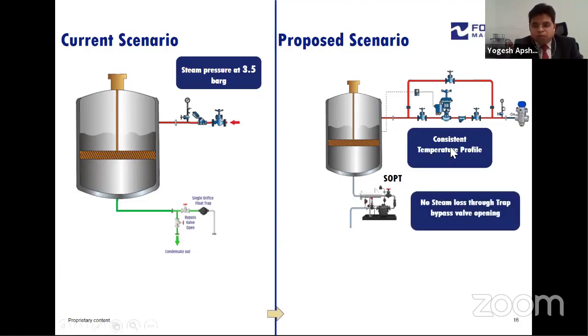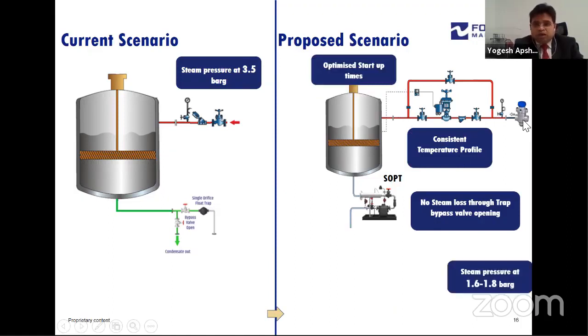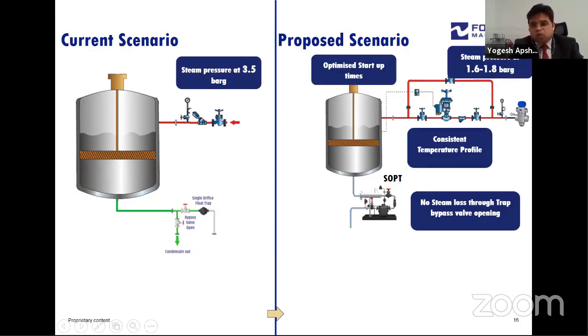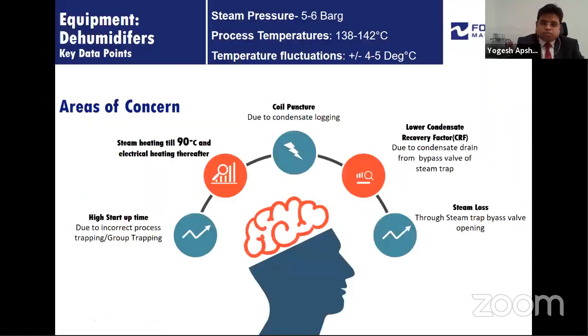So we put a PID based temperature control valve which makes a consistent temperature profile. Then optimize startup times. Then with the PRV, we maintain the pressure of up to 1.6 to 1.8 bar, and with the steam operated pumping trap, we ensure that there is no loss of the condensate.